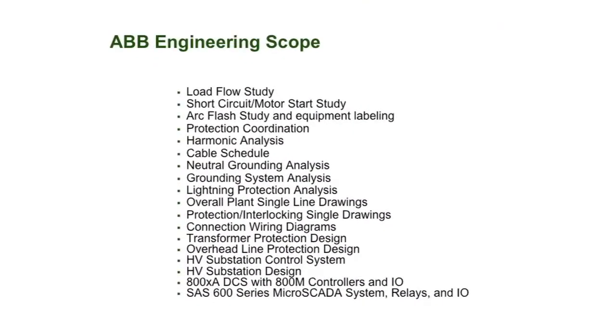And then also the substation automation protection system. Again, we installed a micro-SCADA system, came out of our ABB group in Raleigh, and that took care of all the motorized switches, the relay protection, things like that you need to run the substation. And then going into the engineering scope, we completed all the load studies, the short circuit analysis, the motor studies, the arc flash studies, harmonics. Again, bringing the whole project together, we provided all the arc flash labels for all the electrical panels in the entire plant.